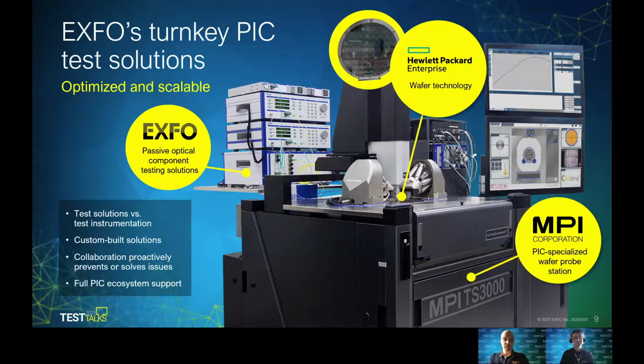So as I already mentioned, that's a 300mm system. It's a semi-automatic system. That means we will load the wafer manually, and then we can automatically step through a wafer, align the fibers, and test the full wafer automatically. This setup is also available in a 200mm version, so for smaller wafers, and is also available with an additional loading option.